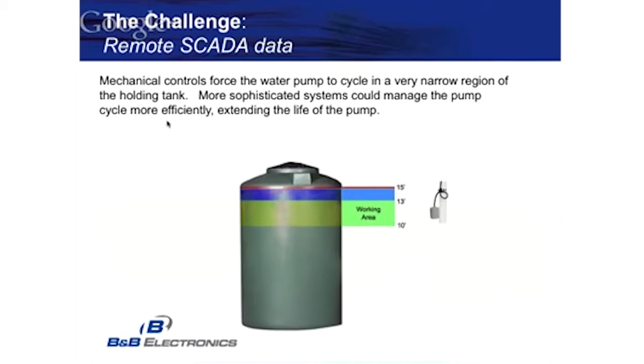This is the effect of a mechanical system, and why intelligence is so necessary. We found that the working area within the holding tank was limited — the system wasn't taking advantage of the entire tank capacity. It wouldn't allow the water to fall below that 10-foot mark, causing the water pump to cycle all the time. An intelligent system would allow you to take advantage of cheaper power, fill the tank at night, and based on demand, fill it so you wouldn't have to cycle so many times.